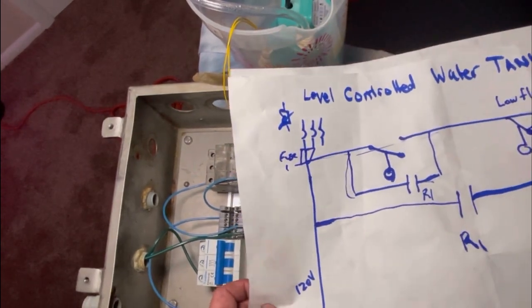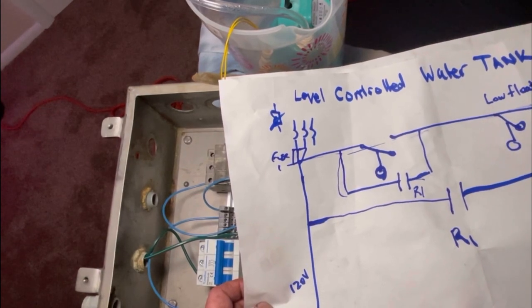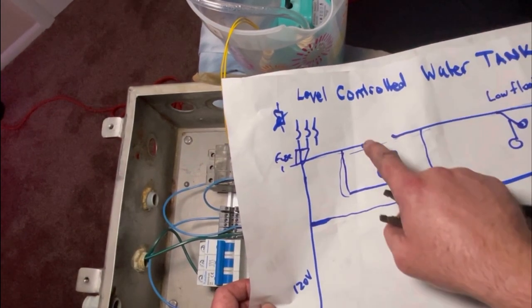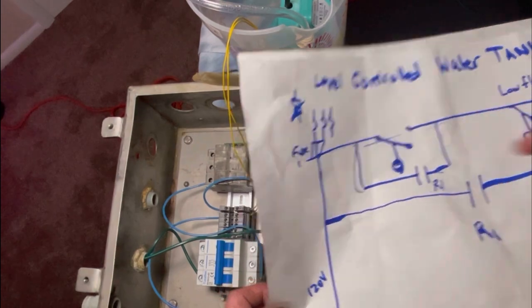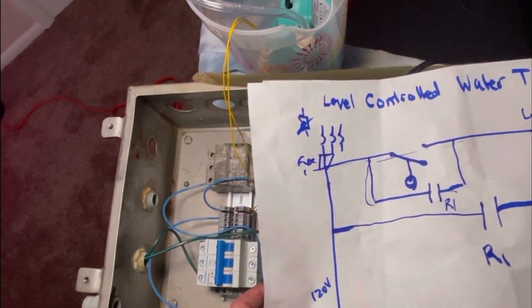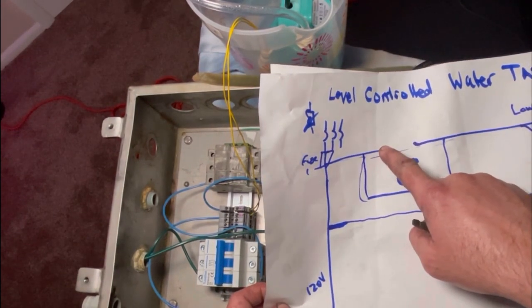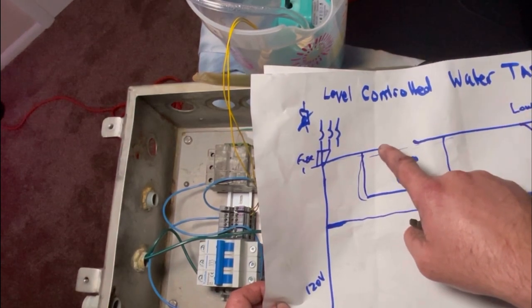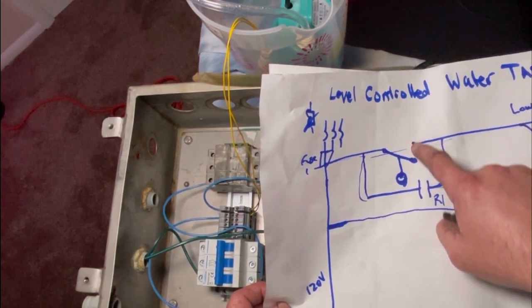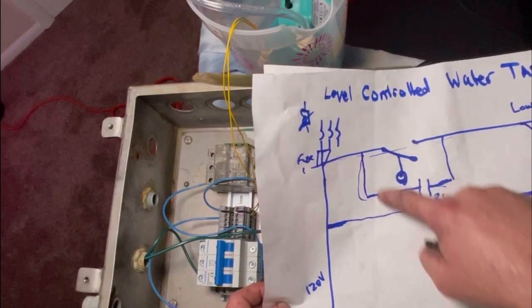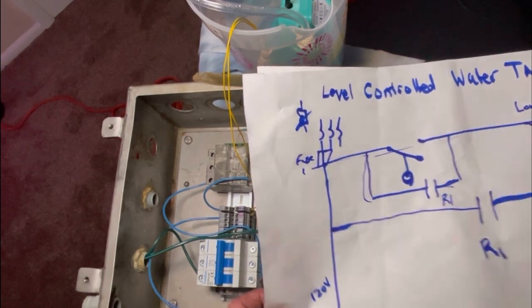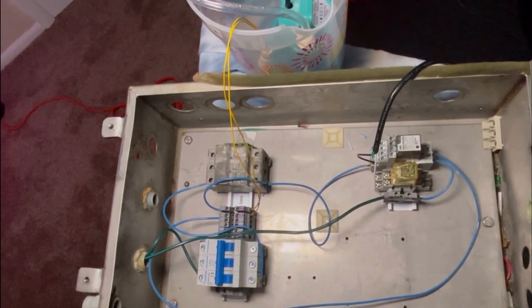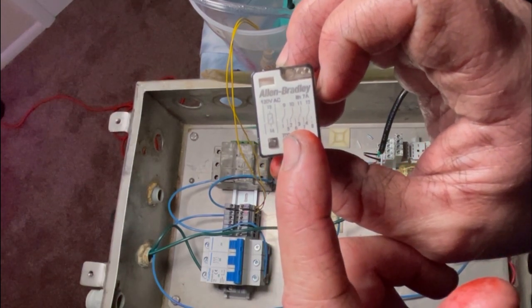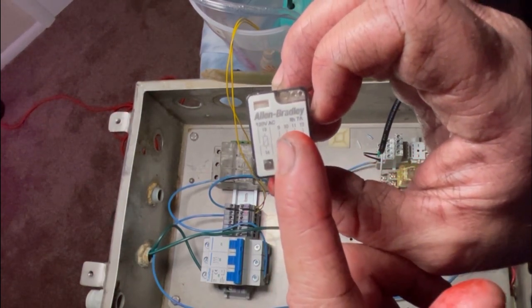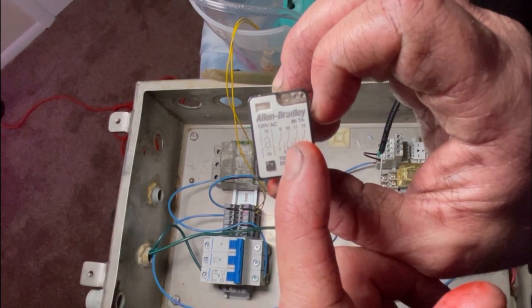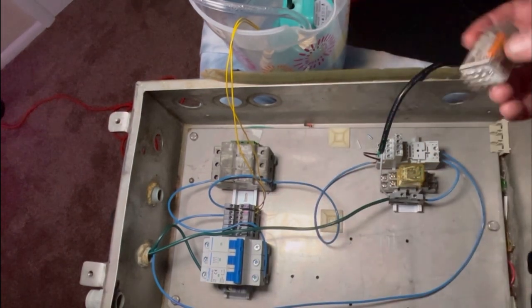If that was confusing, I'm sorry. Another way to do it would be I could go to that terminal. Actually, let me just do it that way to make it less confusing for you guys. Where the terminals are for the floats, I'm going to pull out 2. I'm going to terminate a wire here and a wire here, and I'm going to run it through a different set of normally open contacts on the relay. So let me do that now. 9 and 5. It's going to come in on 9. Normally open terminal is 5. That's what we're going to do.